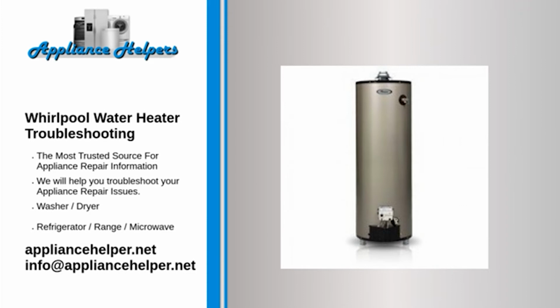Step 7. Troubleshoot a water heater that puts out overly hot water. Check the temperature set screw. It should not be set above 125 degrees F. If the temperature is properly set, then one of the thermostats is to blame. Check for power at both elements. Any element that is getting power while the water is too hot has a faulty thermostat.